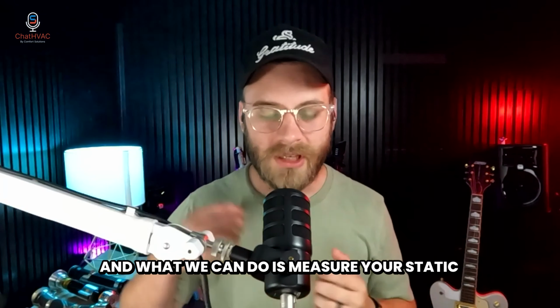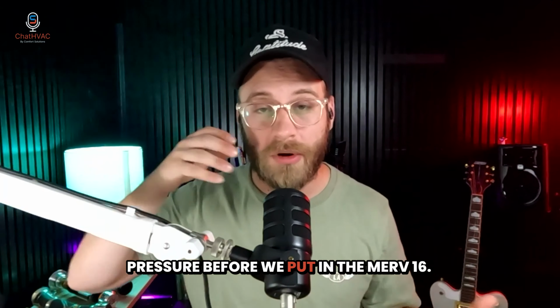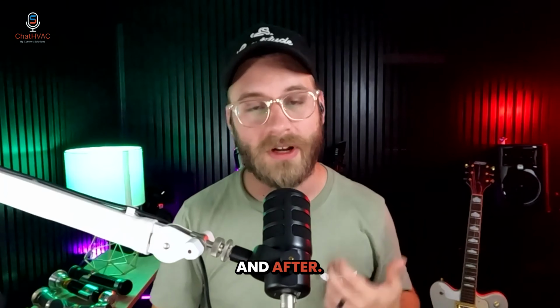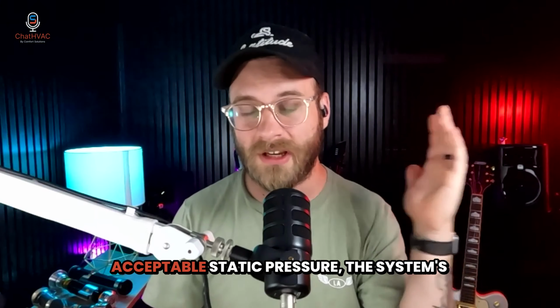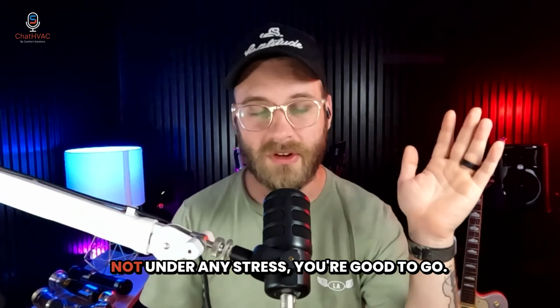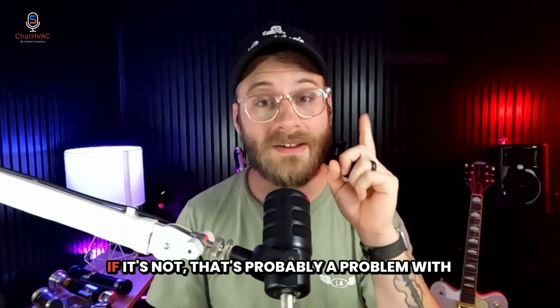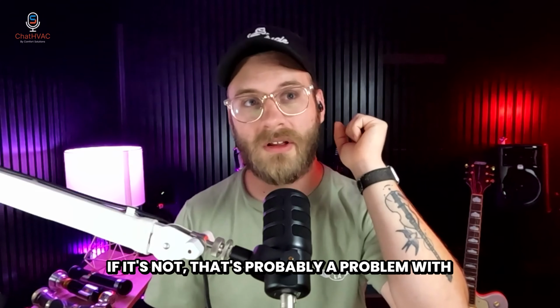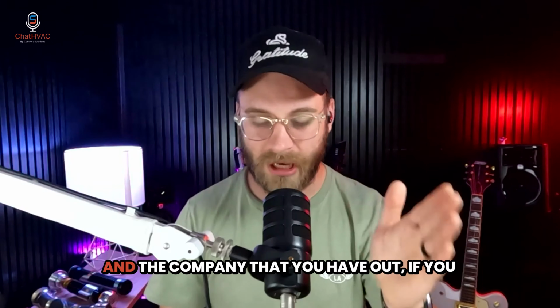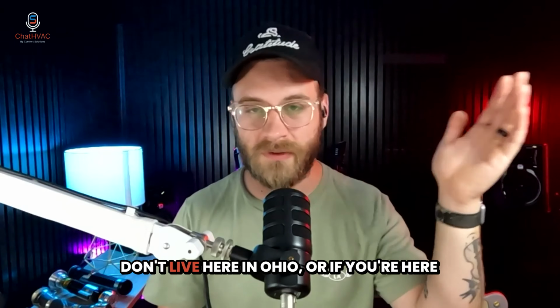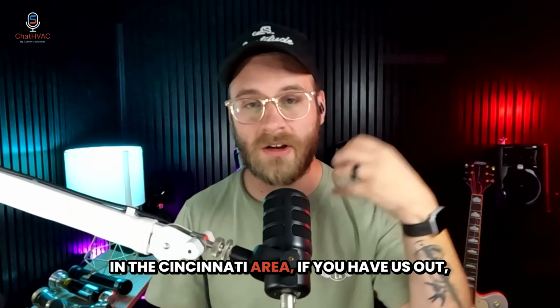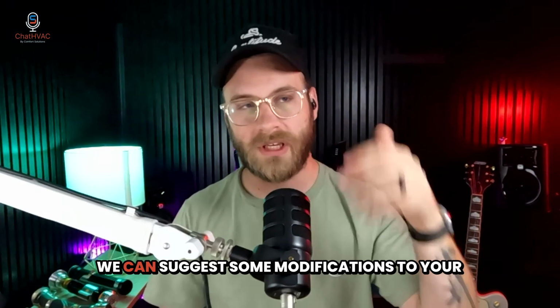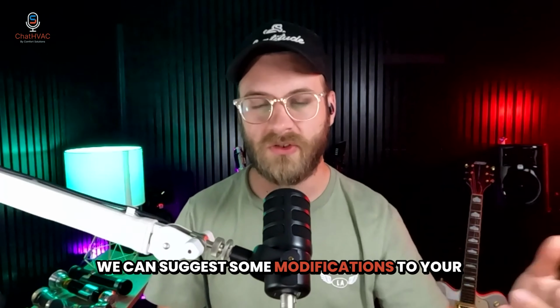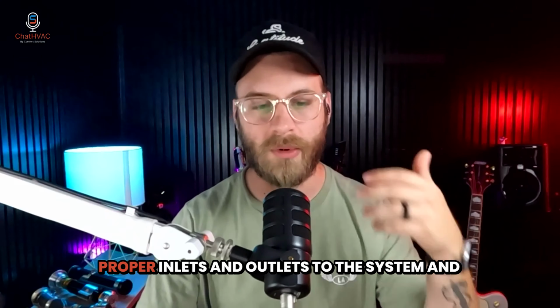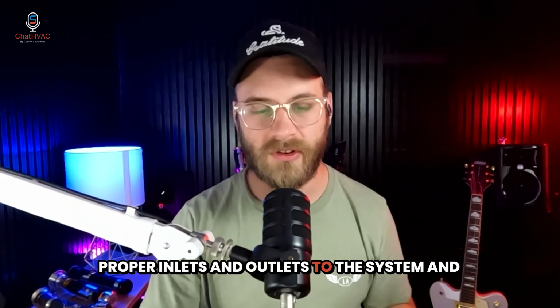And what we can do is measure your static pressure before we put in the MERV 16 and after. And if it is well within the range of acceptable static pressure, the system's not under any stress, you're good to go. If it's not, that's probably a problem with your duct system. And the company that you have out, we can suggest some modifications to your ductwork to be able to allow it to have the proper inlets and outlets to the system and things like that.